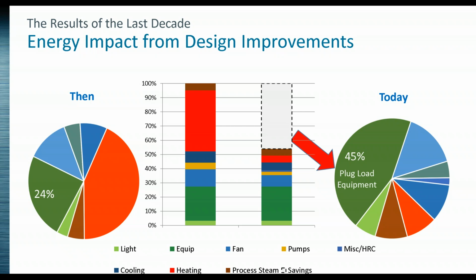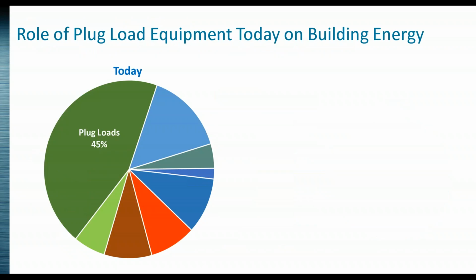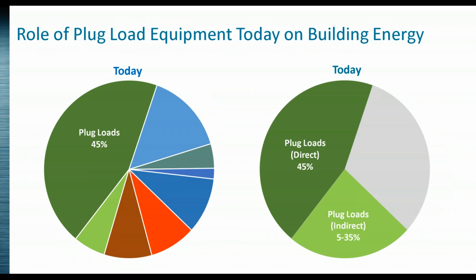A lot of that equipment is plug load, with some process load too. But it's not just the direct component, not just your ultra low temp freezer that's plugged in - it's also the fan energy or pumping energy for your fan coil feeding those spaces, and the conditioning of outside air coming in to provide cooling. So you have both direct and indirect components. What remains in this lab equipment opportunity is really quite significant.